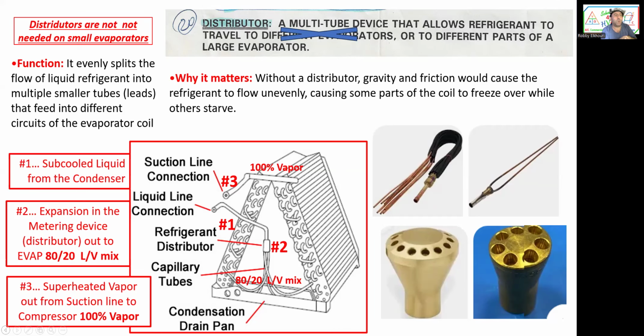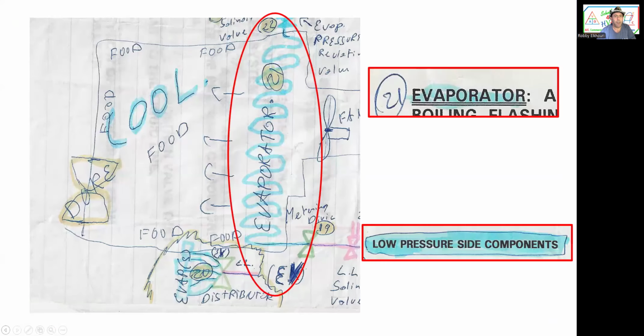So number 1, subcooled liquid from the condenser enters. Number 2, expansion in the metering device and distributor, out 80% liquid-vapor mix, 80-20. And number 3, Freon in the evaporator will evaporate and become superheated vapor, out from the evaporator to the suction line to the compressor. Alrighty, next slide.